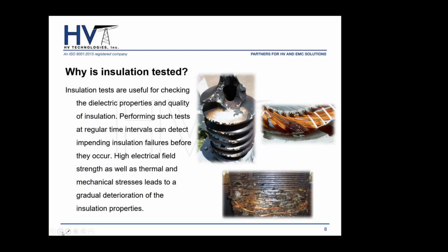So as I mentioned, this is an insulation diagnosis and analyzation system. So why do we test insulation? Insulation tests are useful for checking the dielectric properties and the quality of your insulation. Performing these tests at regular time intervals can detect impending insulation failures before they occur.